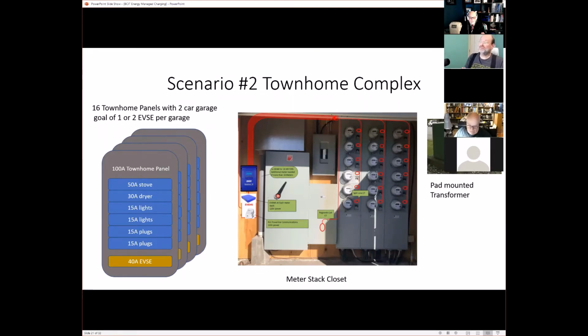And if you're not overloading the panel, you're probably going to overload the pad mounted transformer and the electrical infrastructure between the transformer and the meter stack closet.